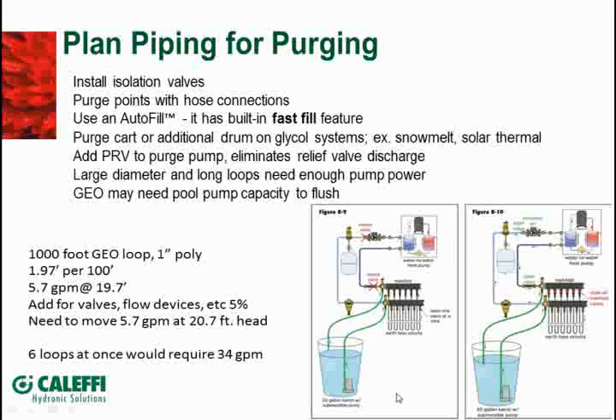So now you can break it into a couple of different subsystems to purge it out and make sure you get all the air out, so you don't have a callback, or a condition where one of your loops isn't exchanging the amount of heat because it's got some air bubbles in it.